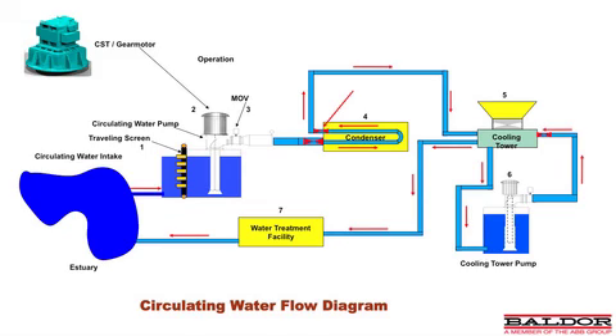then you have at the discharge of the condenser a control valve to control the flow. Exiting the condenser, the water enters the cooling tower. As it exits the cooling tower, it goes back through the water treatment facility and then ultimately back to the estuary. That's your basic, typical circ water pump flow diagram.